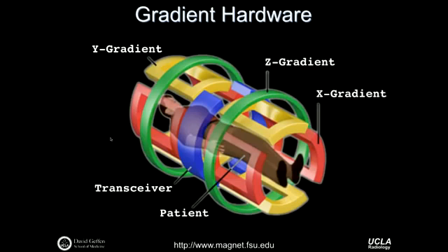A little bit less obvious are these so-called X gradients. There's 4 components in red, 2 at the feet and 2 at the head. And it's really the inner conductor on the inside here and on the inside here that generates a linear variation in the B field near the isocenter, and specifically it does so along the X direction. We'll get into this quite a bit as we go.